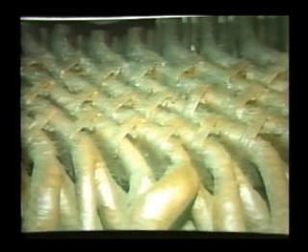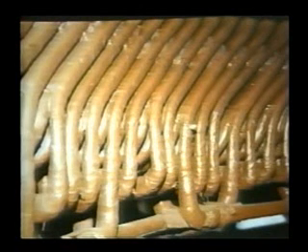And the machine was rewound because of winding failures. In the new winding, the bracing was considerably different. Where there were 3 rows of blocks and ties, there is now 1 row of Dacron felt blocks. On the back side, the coils are tied to the ring, but there are no additional rows of blocks. So somebody made a conscious decision to go with a lesser degree of bracing on this winding as opposed to what was on the original equipment.